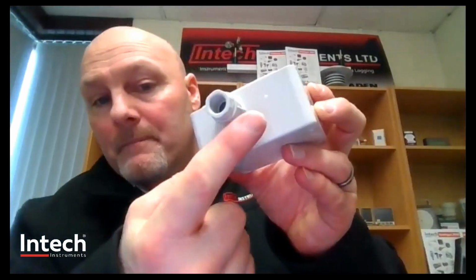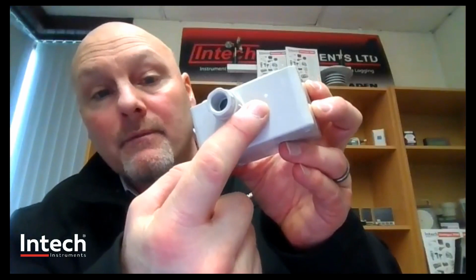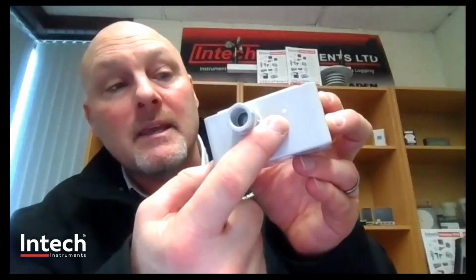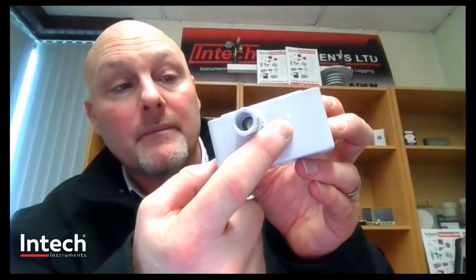down. Now also there are the housings, the connection housings with the hydrostatic level sensors. This one here is the Jumo one, and when it's opened up, you can see the terminations. If you look carefully on the box, I don't know if you can see that very carefully, this is the breather filter, so it allows air to flow, but water not to get in. Obviously, watertight connections and a well IP rated box. We do have a Nivelco brand as well of that model. This is the NAA 102.